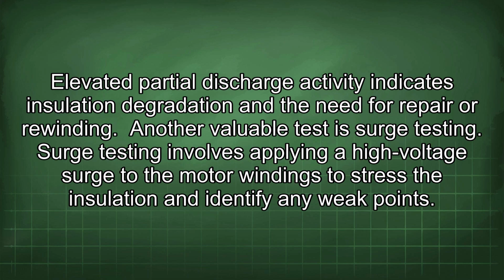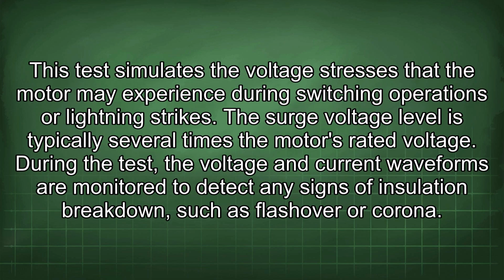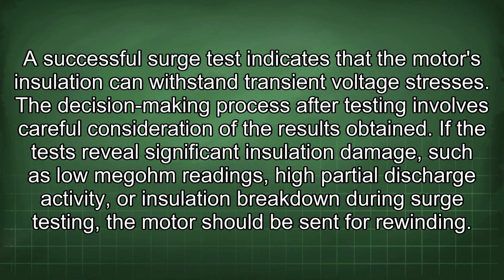Another valuable test is surge testing. Surge testing involves applying a high voltage surge to the motor windings to stress the insulation and identify any weak points. This test simulates the voltage stresses that the motor may experience during switching operations or lightning strikes. The surge voltage level is typically several times the motor's rated voltage. During the test, the voltage and current waveforms are monitored to detect any signs of insulation breakdown, such as flashover or corona. A successful surge test indicates that the motor's insulation can withstand transient voltage stresses.